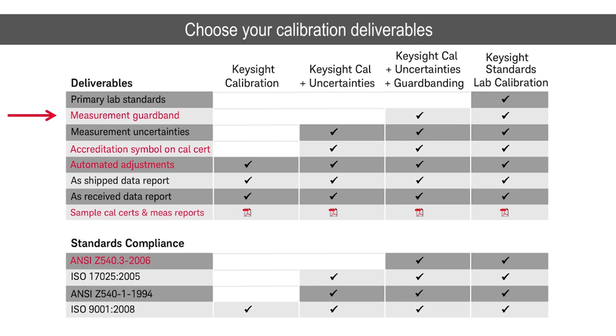Moving down to measurement guard band, if the device you send in has a specification and part of the job is to check and see whether it passed or failed, we will apply an expanded measurement uncertainties guard band. However, if it is an item which requires only a characterization, such as a power sensor when you're looking at the calibration factor, then we simply provide the calibration factor and the uncertainty associated with that. You will receive always both the data that we measured and the measurement uncertainties, and because we are accredited in all of the parameters corresponding to these measurements, you will receive the accreditation body symbol.